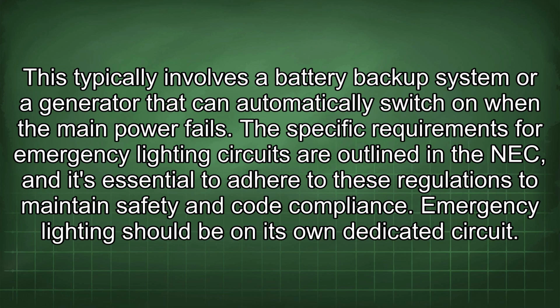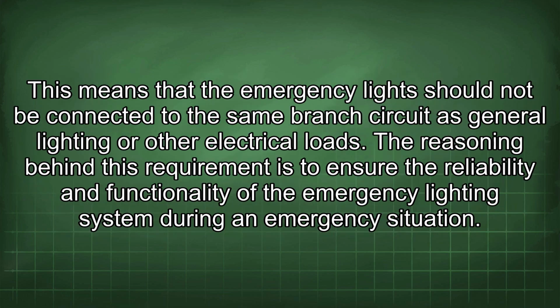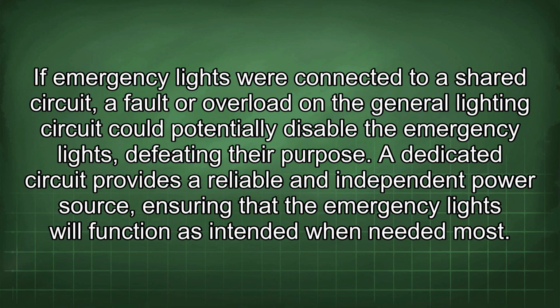Emergency lighting should be on its own dedicated circuit. This means that the emergency light should not be connected to the same branch circuit as general lighting or other electrical loads. The reasoning behind this requirement is to ensure the reliability and functionality of the emergency lighting system during an emergency situation. If emergency lights were connected to a shared circuit, a fault or overload on the general lighting circuit could potentially disable the emergency lights, defeating their purpose.